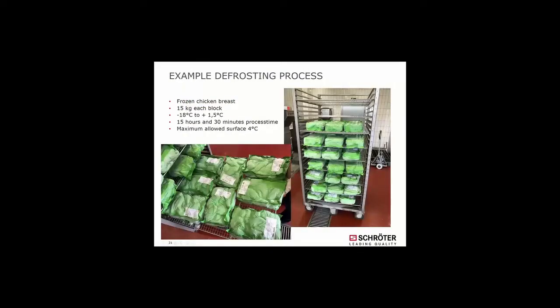There were blocks of each of them of 15 kilograms in a vacuum package. The aim was to defrost the product from -18 to +1.5 degrees. That means we have to go through a phase change from solid to liquid, which needs a lot of energy and time. Therefore, we reached a process time of 15 hours and 30 minutes.